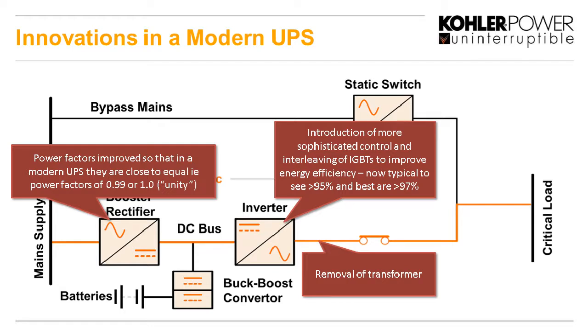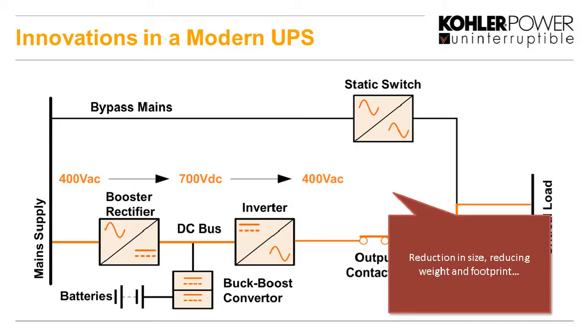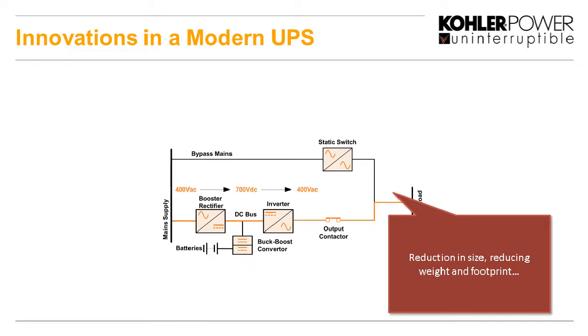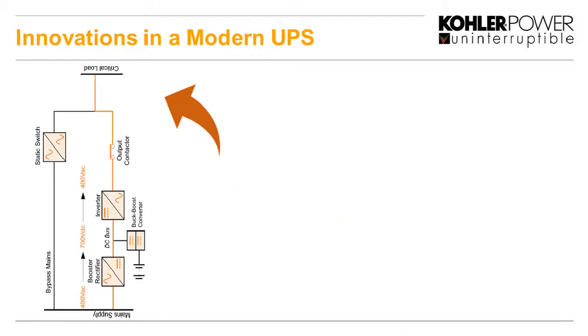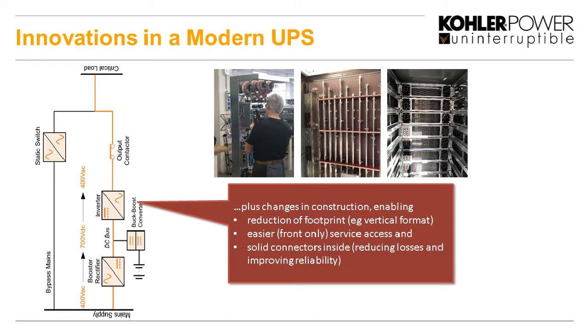We've also recently seen quite big changes in the inverter with much more sophisticated control of the actual inverter devices, the IGBTs. And we have now interleaved 3-level IGBT inverters, and these are pushing the actual boundaries of efficiency up to their best ever of over 97%. So all these advances have allowed us to make a reduction in the size, reducing the weight and the footprint of the actual UPS system itself into a point where we can actually put it into a modular design. And we've seen here that we can now put these small UPSs into cabinets, which are all front access with solid connectors, making the losses even less, making it much easier to service, and the whole thing's much smaller and neater and much more suits the modern environment.